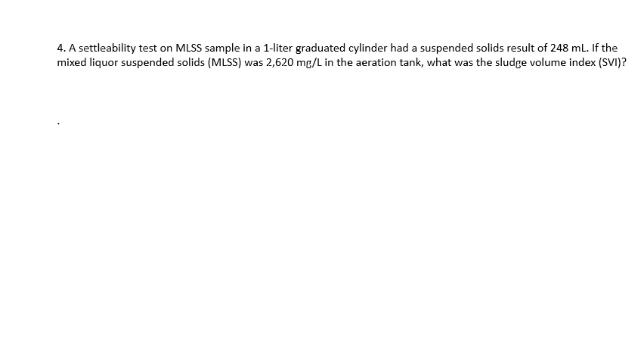A settleability test on an MLSS sample in a one-liter graduated cylinder had a suspended solid result of 248 milliliters. If the Mixed Liquor Suspended Solids was 2620 milligrams per liter in the aeration tank, what was the Sludge Volume Index? Pull out your knowns and unknowns: 2620 mg/L and 248 mL/L, and we're looking for the SVI.